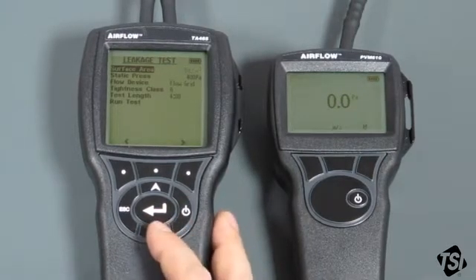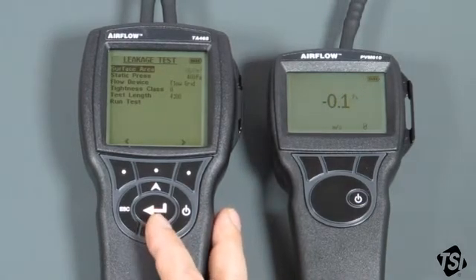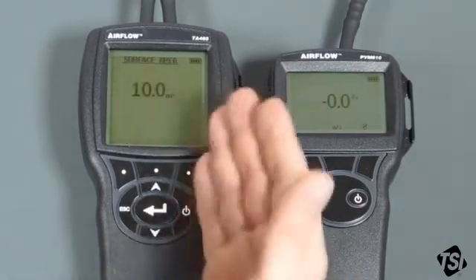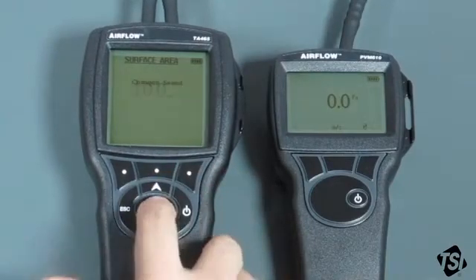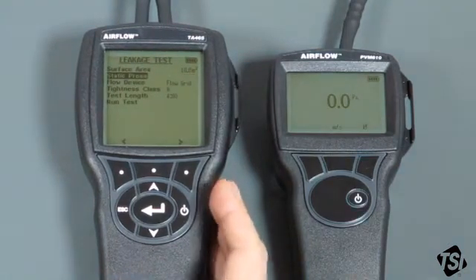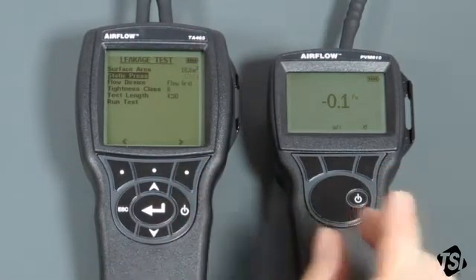The surface area is the surface area of the ductwork system that you're about to test. Please don't get this confused with the cross-section area of the duct — it is actually the surface area of the outside of the duct, so you need to have that value measured and ready for when you do the test. In this case we're going to assume that it's 10 metres squared. Move down to the next option which is static pressure. Static pressure is the pressure that you're going to maintain the ductwork system at while you're carrying out the test. You'll monitor the static pressure on the PVM610.